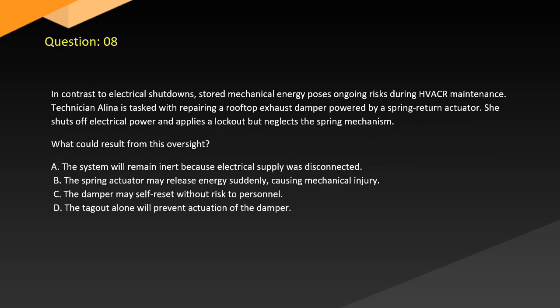Question 8. In contrast to electrical shutdowns, stored mechanical energy poses ongoing risks during HVACR maintenance. Technician Alina is tasked with repairing a rooftop exhaust damper powered by a spring return actuator. She shuts off electrical power and applies a lockout but neglects the spring mechanism. What could result from this oversight? A. The system will remain inert because electrical supply was disconnected. B. The spring actuator may release energy suddenly, causing mechanical injury. C. The damper may self-reset without risk to personnel. D. The tagout alone will prevent actuation of the damper.